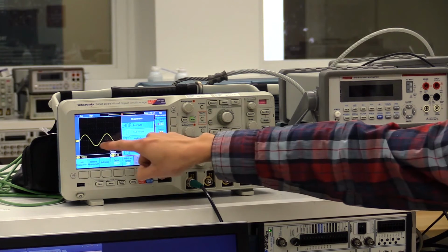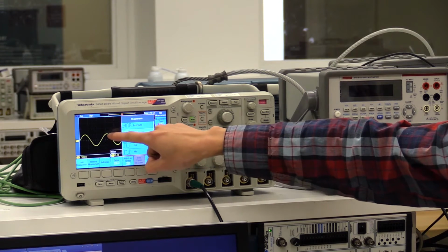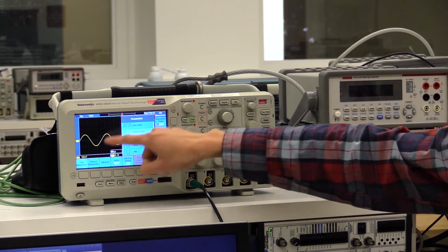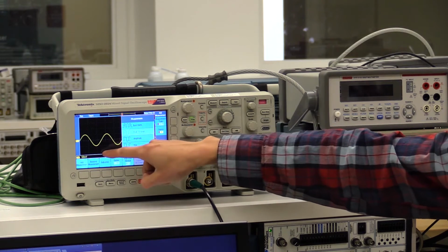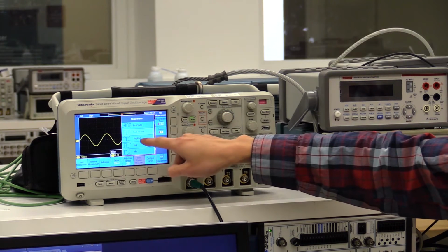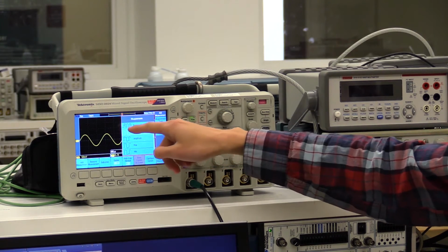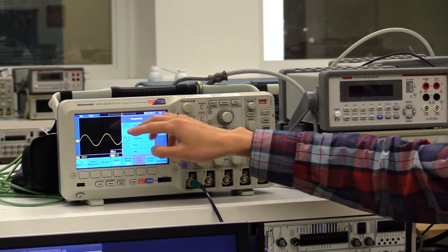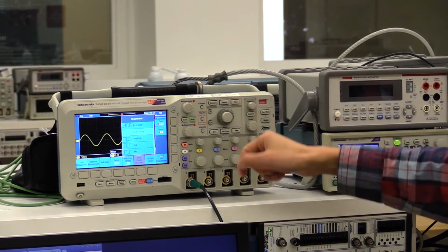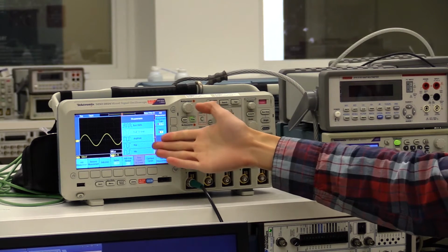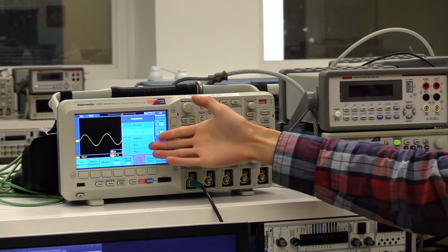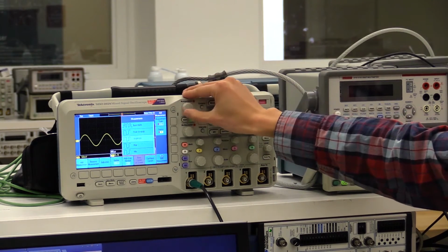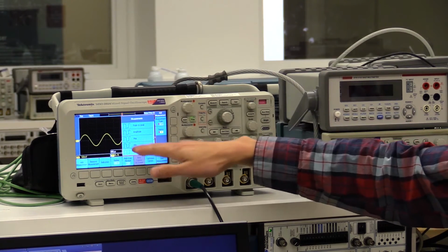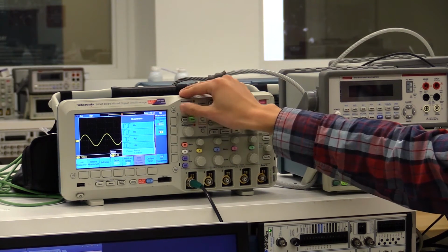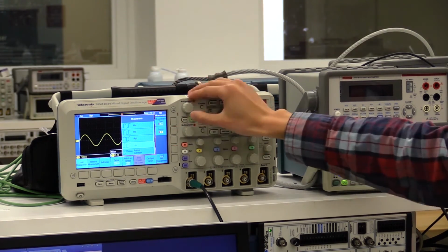However, if this is a noisy signal, say there's a spike here or a spike down there, peak to peak will take the bottom of the spike to the top of the spike, whereas amplitude will ignore most of the spikes and just give you the signal of the wave. And similarly, max and min will do the same thing, except it'll only look at the max or the min, or high would be without the spikes, and same with low. Low would be without the spikes.